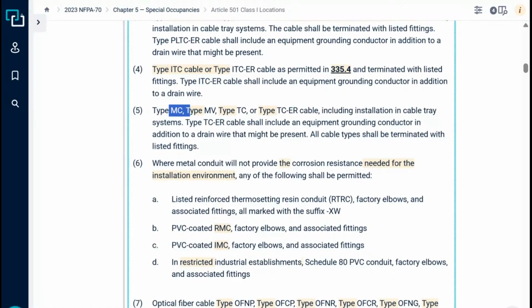So that's why it's so important to get familiar with it, okay? Because here, I am not going to use MC-HL for this. Hell no. I'm going to use MC, okay? If I've got cable trays, I'm going to use type TC and type TC-ER. Okay, the difference in the ER is the ER allows it to extend beyond the tray, whereas TC does not. Okay, that type of application. And it can get deeper than that. It can deal with whether or not there's an equipment ground involved and what size of the conductors and how many conductors are inside the tray cable that can signify whether or not you can mark something as an ER or not. We can get into that in another episode if you want to learn the nuances of tray cable and how the construction is.